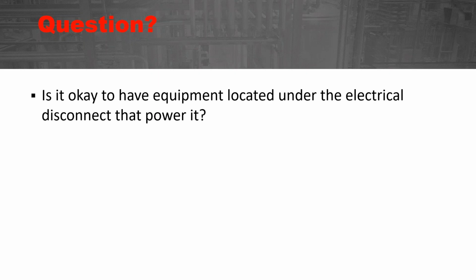What I see again and again out there is that the industrial control panel has a disconnect, usually in the upper right corner, where you can turn the breaker on or off, but the conductors coming in the top are still energized on the line side. We have to be careful of that. If we're going to work within 12 inches of that energized part, the conductors, we have to be suited up. In fact, if you're in the arc flash boundary of the conductors in the top, you have to be suited up for arc flash. So it probably is good, but go make sure the installation complies with the National Electrical Code.